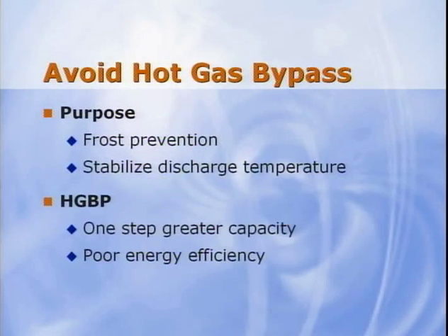In this latter case, a rule of thumb concerning hot gas bypass is that it will increase the stage of compression one step beyond a system without hot gas bypass. It isn't hard to comprehend the additional energy required to run a system one step higher than it may need to operate, even if this is just part-time. It's a rare case indeed to find a traditional VAV system that actually requires hot gas bypass. But if one is found, then the hot gas bypass by definition must work. In that case, it must control well and be well controlled so that it doesn't waste energy.